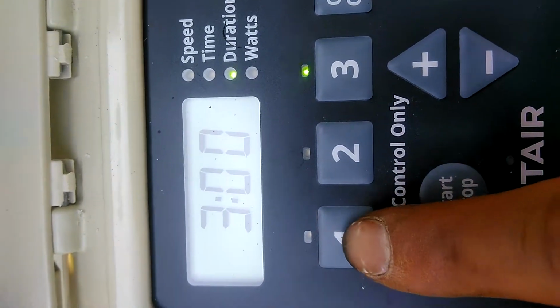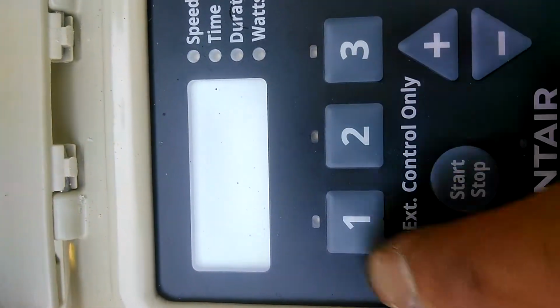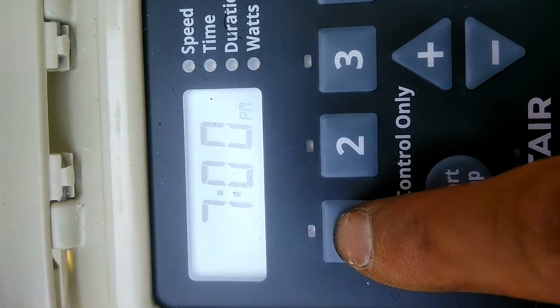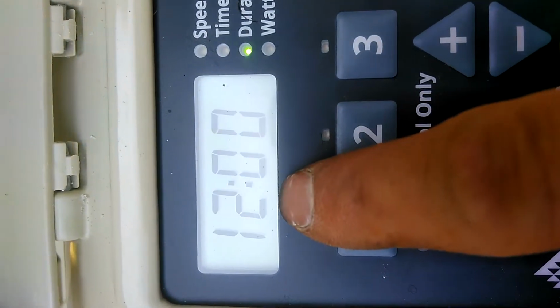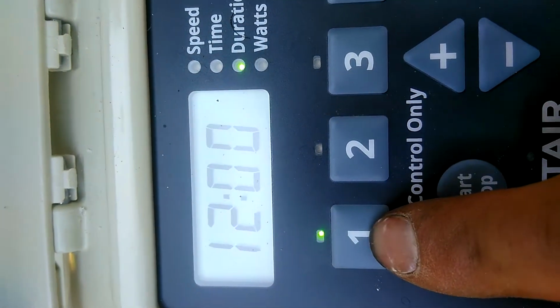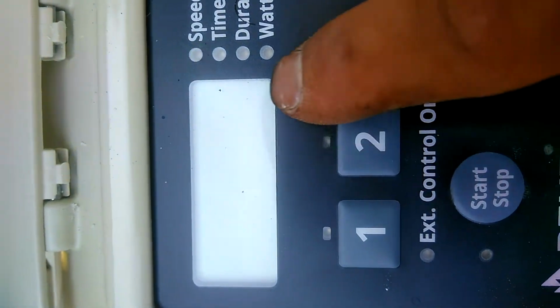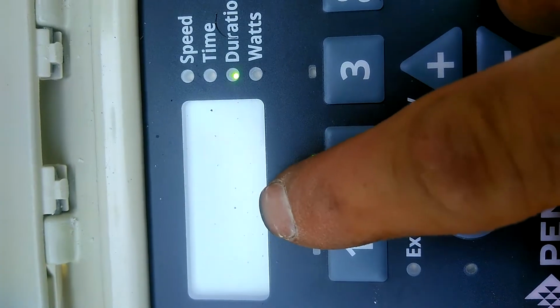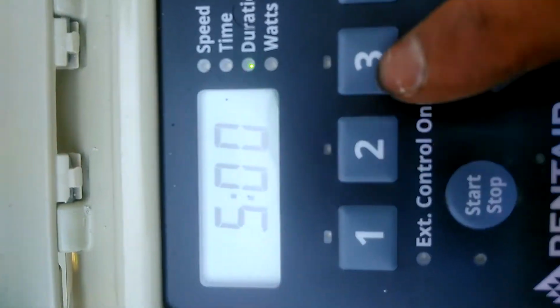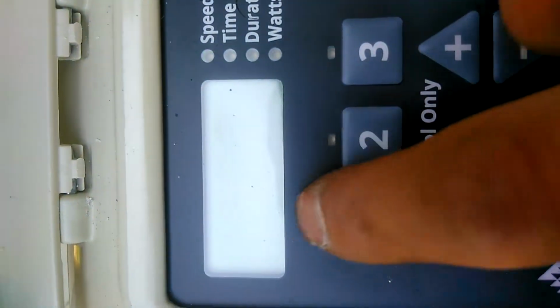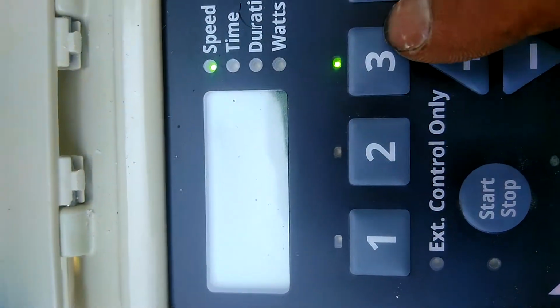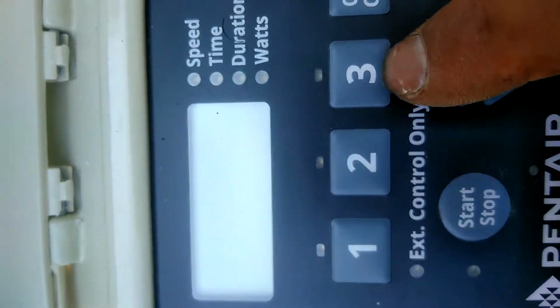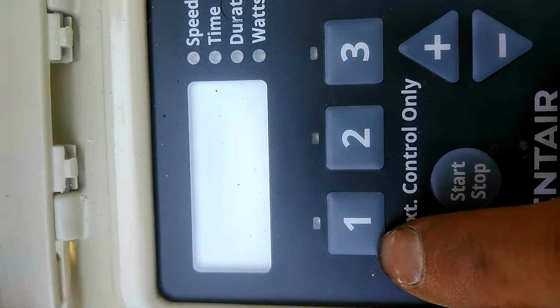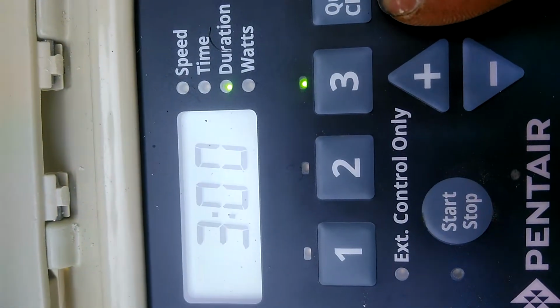So just to recap, I've got speed 1, which is 2,000. That's my normal running speed, starting at 7 p.m., running for 12 hours, which will shut off at 7 a.m. Then the pump will automatically go to speed 2, which is 0 RPM. So the pump will be off at this time, and it's going to be off for 5 hours. That brings me to noon. And then at noon, speed 3 will start, which is a regular speed of 2000. And it's going to run for 3 hours until 3 p.m. and then shut off. Then my pump will turn back on at 7 p.m. and restart the whole schedule again. Okay?